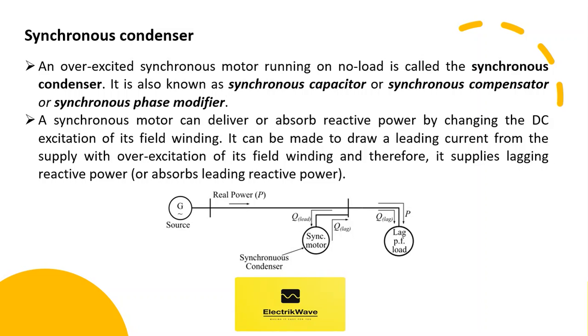It can be made to draw a leading current from the supply with over excitation of its field winding, and therefore it supplies lagging reactive power or absorbs leading reactive power.